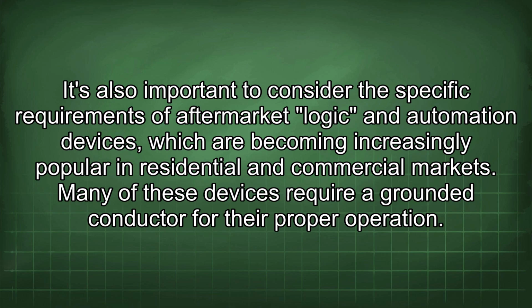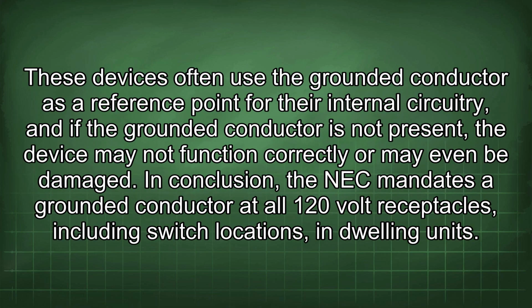It's also important to consider the specific requirements of aftermarket logic and automation devices, which are becoming increasingly popular in residential and commercial markets. Many of these devices require a grounded conductor for their proper operation. These devices often use the grounded conductor as a reference point for their internal circuitry, and if the grounded conductor is not present, the device may not function correctly or may even be damaged.